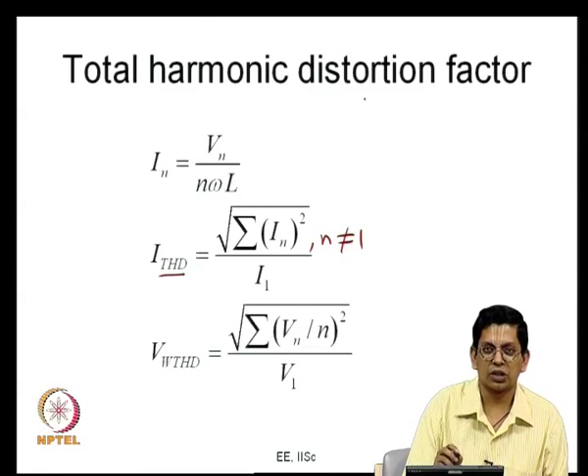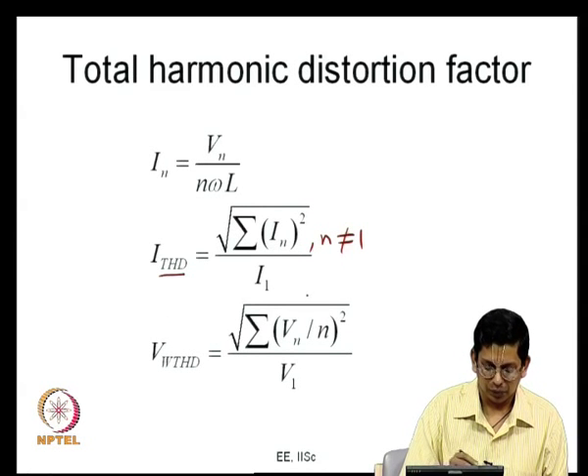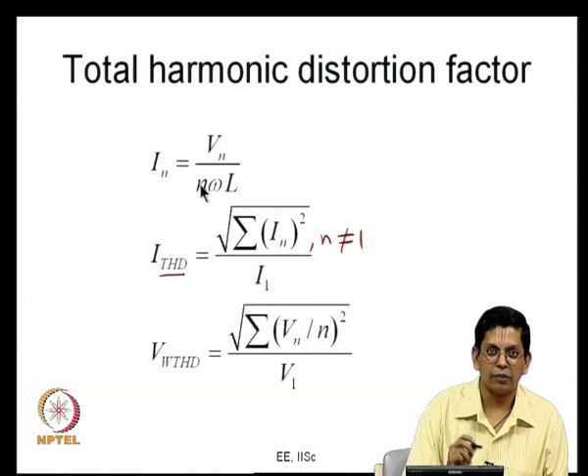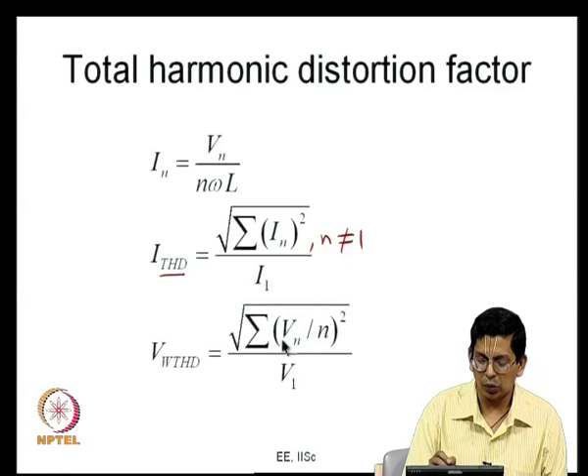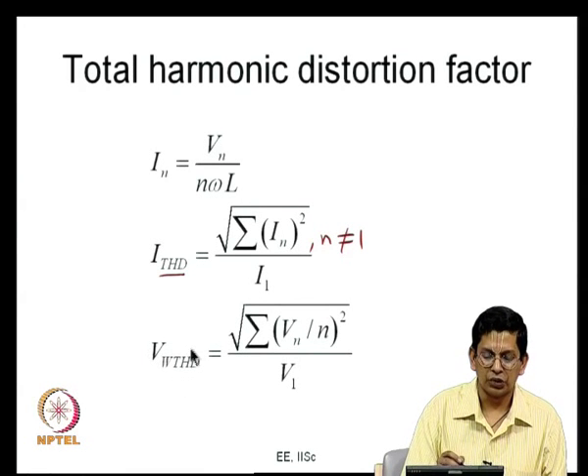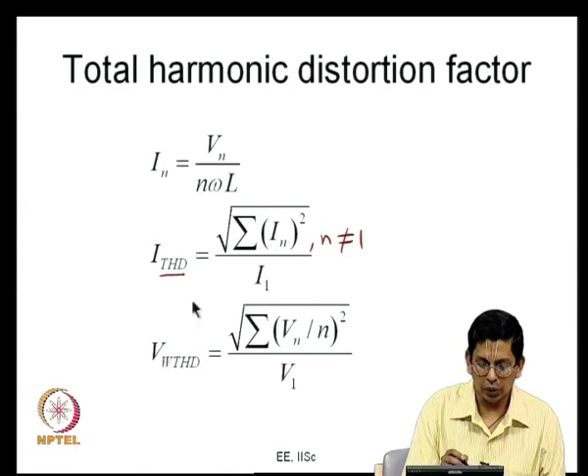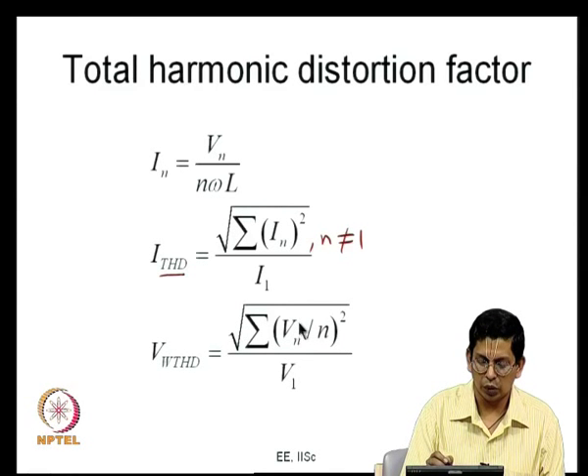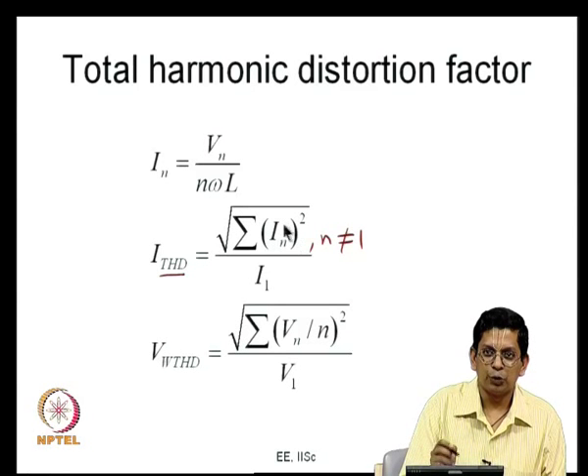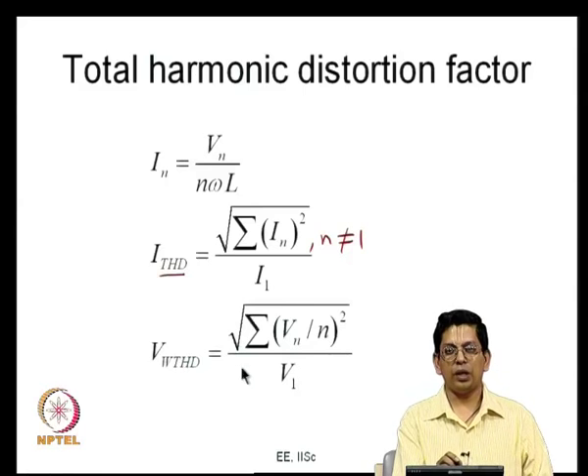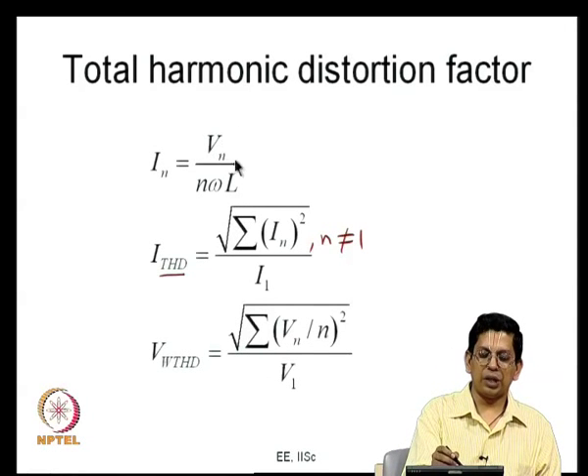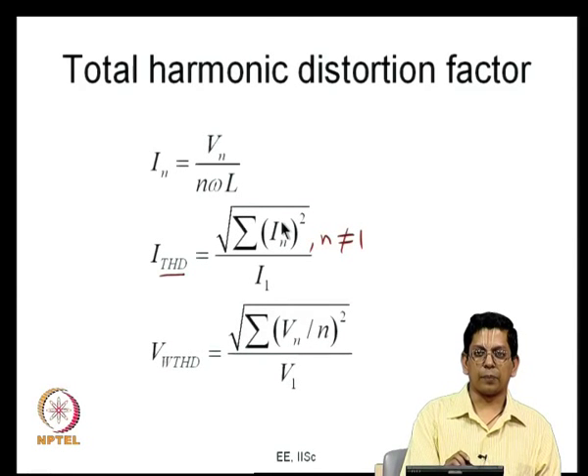The total harmonic distortion (THD) of the current waveform is the RMS sum of all harmonic currents divided by the fundamental current I1. Since In is proportional to Vn/n, the sum of (Vn/n)² is a measure of the sum of In², and dividing by V1 gives the weighted total harmonic distortion factor of the voltage waveform, which equals the current THD. To compute weighted THD, individual harmonic voltages must be calculated from the harmonic spectrum.